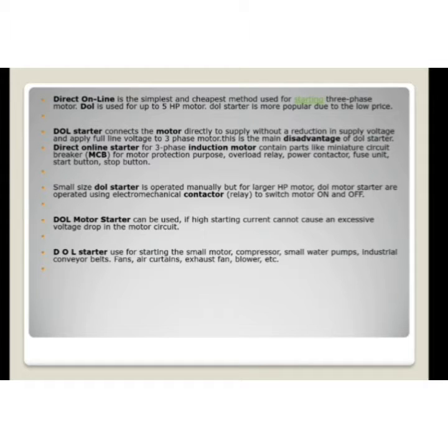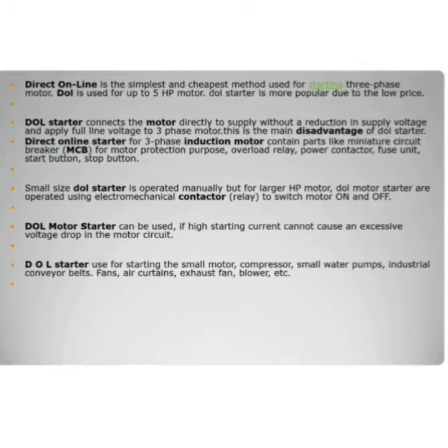It is the simplest and cheapest method for starting a 3-phase motor. The DOL starter is generally used for small rating motors, such as 5 horsepower motors. It is very popular due to its low price. The use of the DOL starter is restricted to smaller rating motors, as these starters do not limit the starting current. The essential elements of the DOL starter include the main contactor and protective devices. Let us discuss the DOL starter in detail.